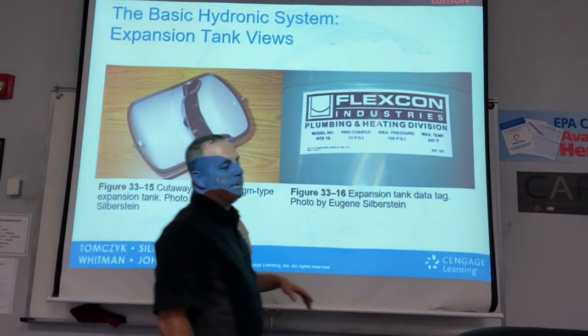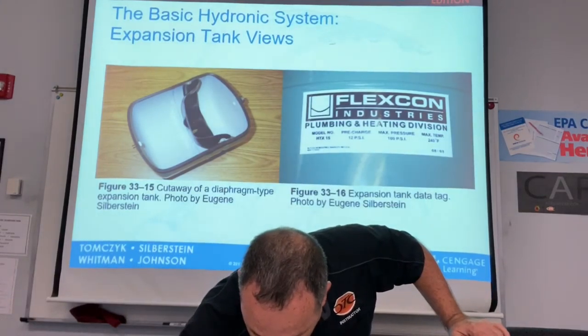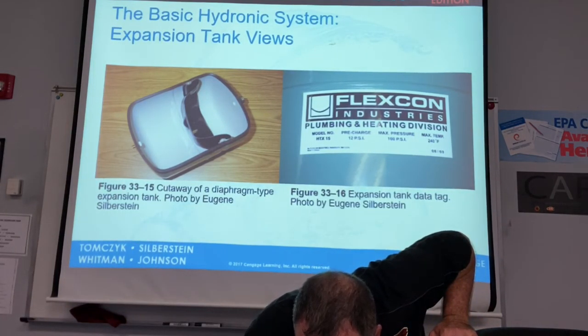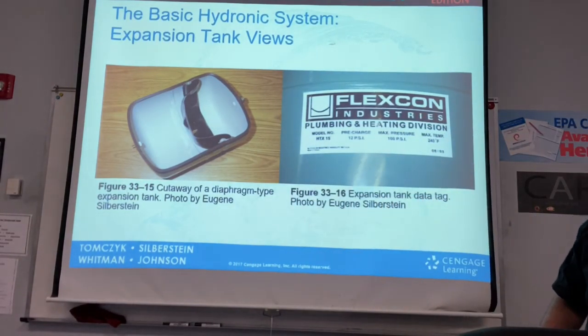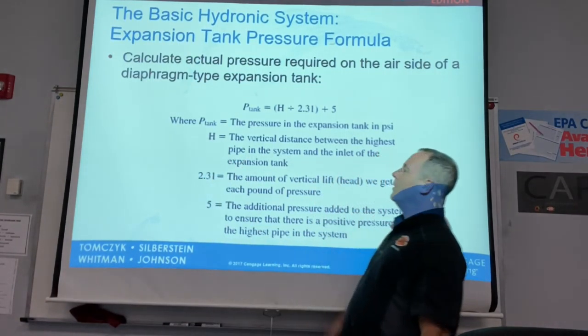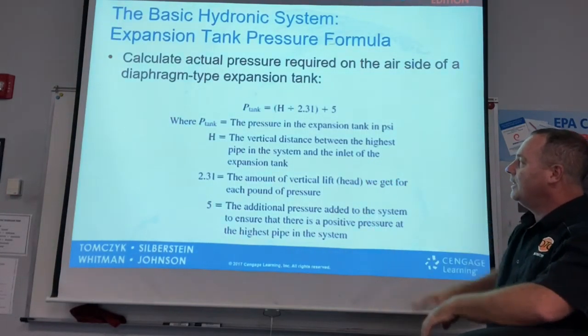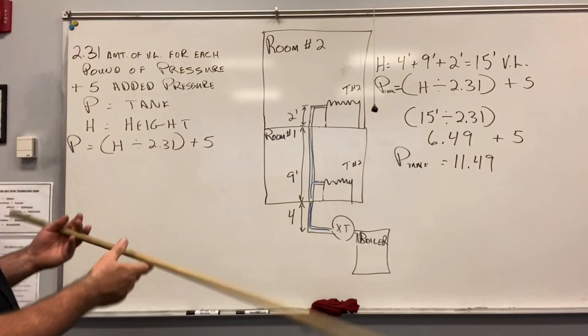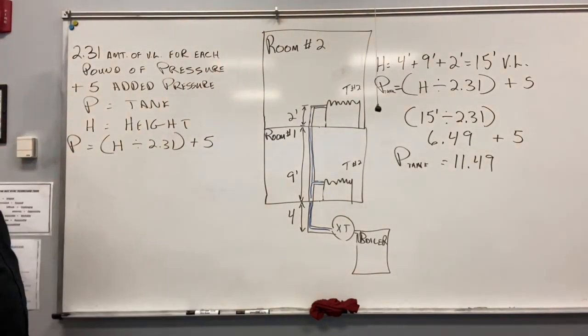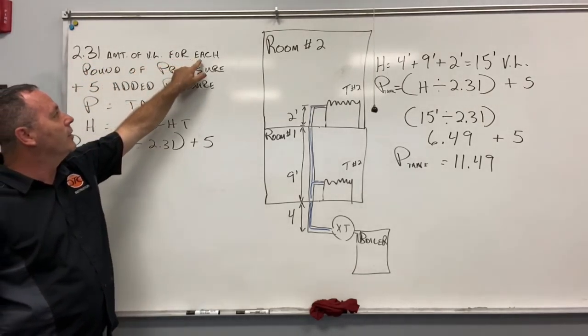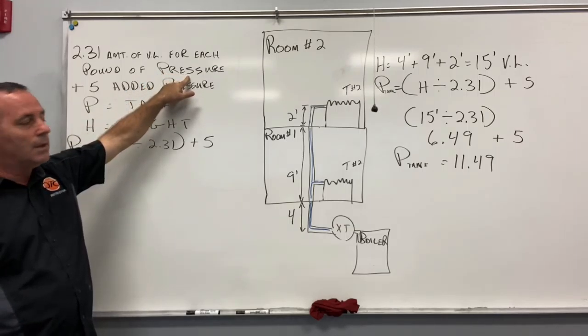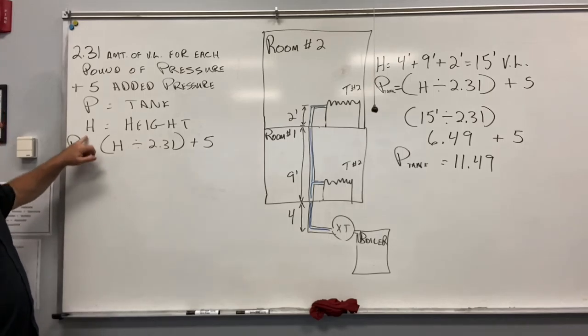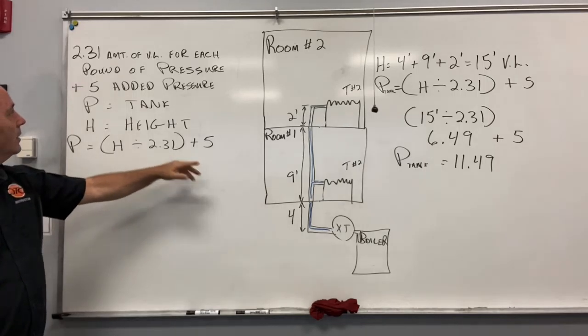To determine the actual pressure for an expansion tank, we must measure the vertical distance between the highest pipe and the expansion tank inlet and use it in a formula from page 975. The formula is: P(tank) = (H ÷ 2.31) + 5, where H equals height in feet, 2.31 is the vertical lift per pound of pressure, and 5 is added pressure.